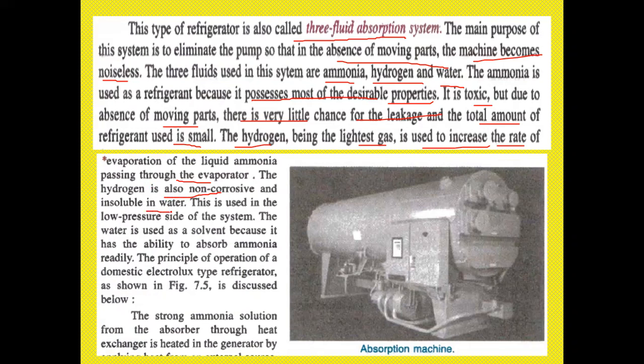This is used in the low pressure side of the system. The third fluid is water, which is used as a solvent because it has the ability to absorb ammonia readily. Therefore, the principle of operation of the domestic Electrolux type refrigerator is shown in figure 7.5 described below.